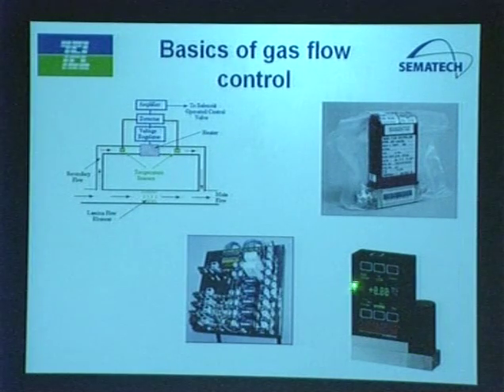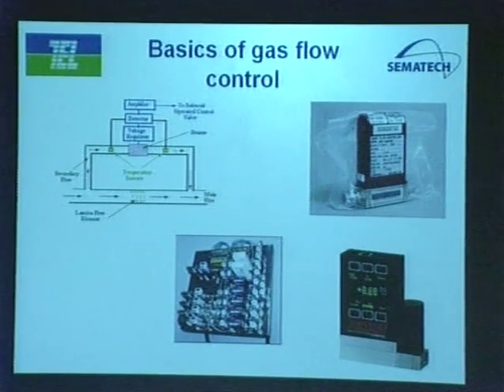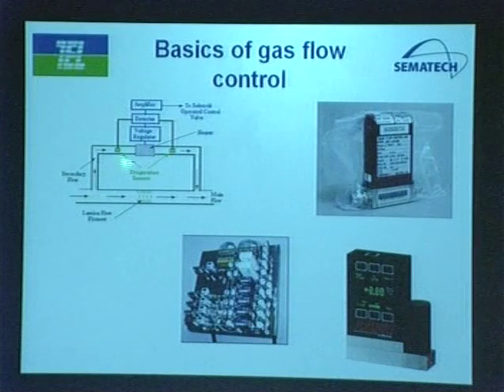This is really a transducer, a straightforward one, and I'll explain a bit how it works. Gases have properties, especially with heat, so you can program this unit to work with a particular gas at a particular heat capacity. These systems monitor the heat flow between two sensors within them, and raise or lower a valve to change that flow of heat, so you get the amount of gas delivered to your chamber that you're asking for.